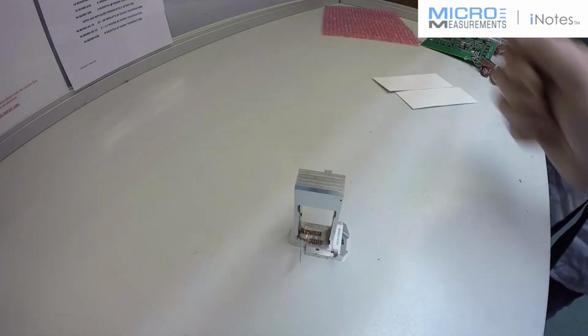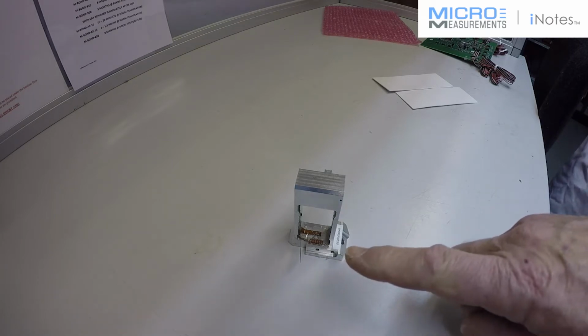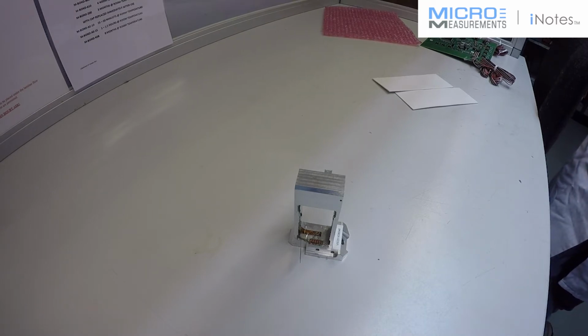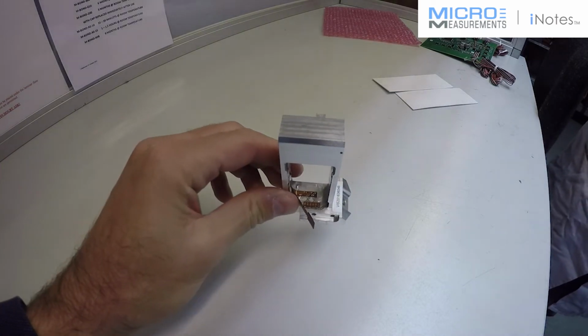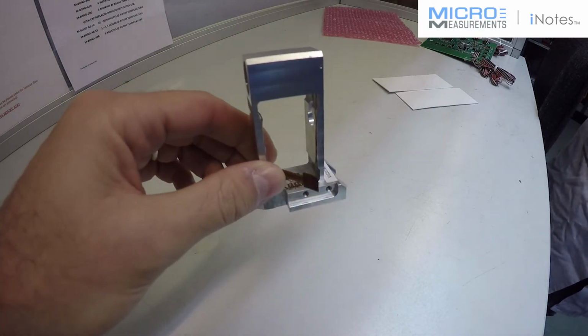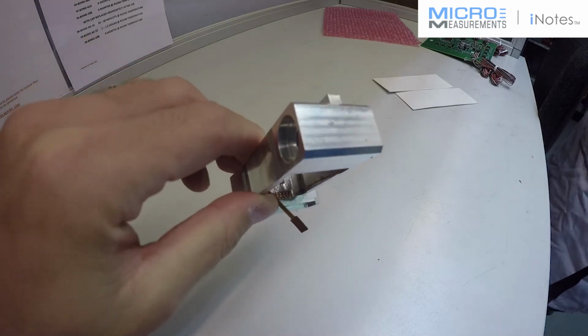Again, we'll be using our epoxy phenolic M-Bond 600 adhesive in this case because of its being aluminium. Yes. And the printed circuit board that's coming off here, or the flexi circuit, is all part of the process here, is it? Indeed, yeah. The gauges are wired using our 34 AWG solid copper enamel coated wire to a terminal, which is then connected to the flexible circuit, which then goes into the customer's final electronics.